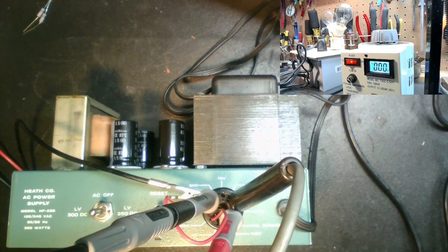I'm at 600 volts on my digital multimeter, which will be checking for the 300 volts DC to begin with - it's probably going to be closer to 350 without load. And we'll be looking for probably 750, 770-ish on the high voltage, maybe up to 800 volts. But we're going to bring it up slowly.